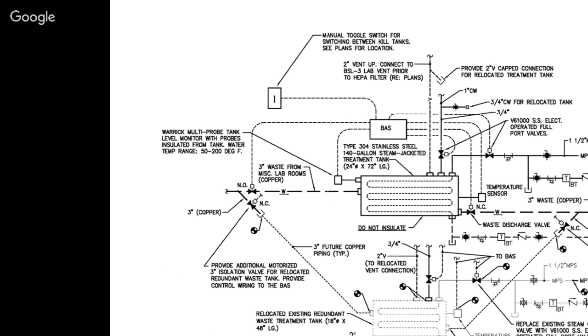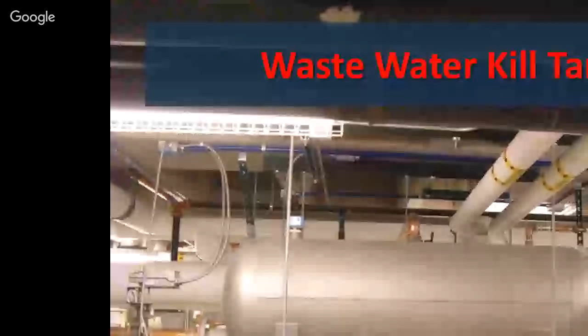We controlled the heat wire during commissioning. We boiled the water, and 200 degree vapor went up the pipe, got to the PVC, warped the pipe, and then hit the interstitial space. And that had to be replaced with copper. So that was a big lesson learned. That vent pipe should have been a separate pipe out of the roof, and that would never have been an issue. Here's a picture of the final installation. I think these pipes were insulated at the end, but it's just a real simple tank with an inlet and outlet pipe, vent pipe coming up top. This is the steam heat exchange pipe going in.